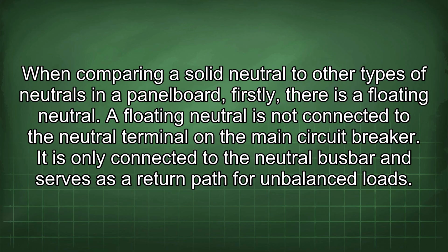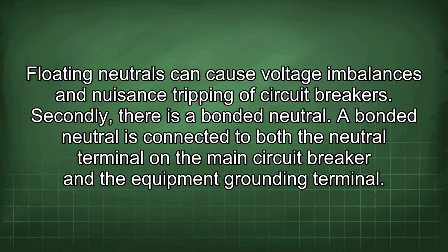A floating neutral is not connected to the neutral terminal on the main circuit breaker. It is only connected to the neutral busbar and serves as a return path for unbalanced loads. Floating neutrals can cause voltage imbalances and nuisance tripping of circuit breakers. Secondly, there is a bonded neutral. A bonded neutral is connected to both the neutral terminal on the main circuit breaker and the equipment grounding terminal.